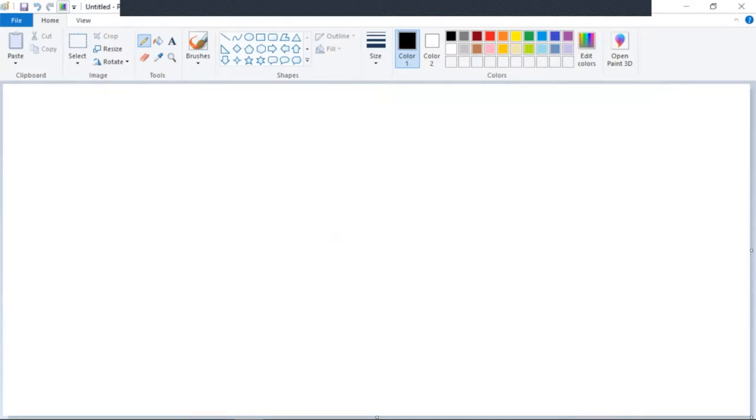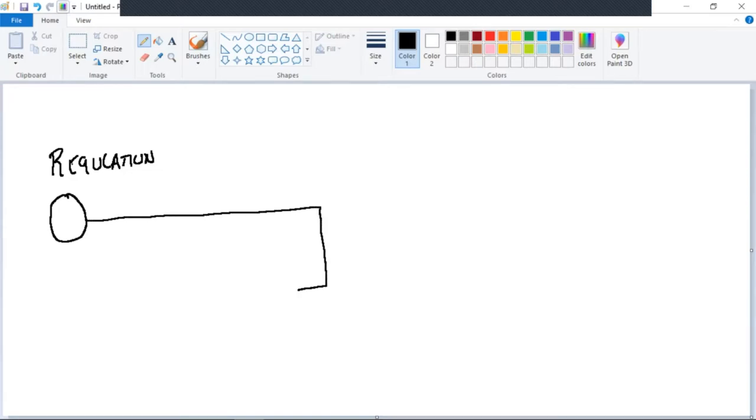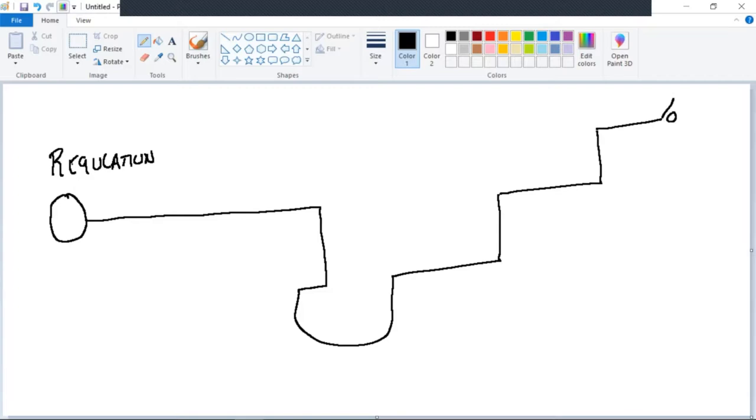Don't save. Okay. So here's the purpose of a voltage regulator. And I'm going to just do one, even though there are three on a circuit, for you to understand. So I'm regulating voltage at a substation. Its purpose, you remember, I've got a feeder line that's coming out here and it's going all different directions. It's coming up in here until it eventually meets an open point. And then I've got a feeder coming from somewhere else. The purpose of a voltage regulator on this entire circuit, remember, I've got transformers, I've got tap lines going off. All right, this thing's pretty loaded up.